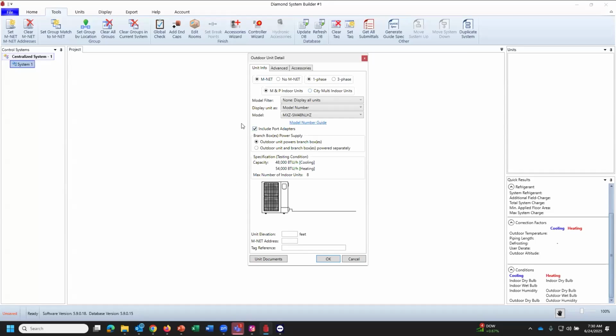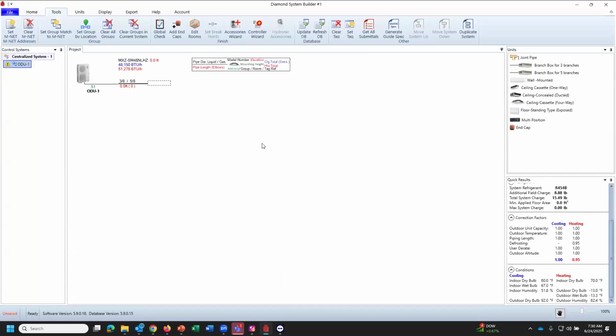We're going to include all of our port adapters. We're going to say the outdoor unit is going to power my branch box. We're going to install this at 0 feet, and that address is going to be 51 because this is going to be a single outdoor unit system. I'm going to go ODU-1 because even in residential, I name all my units.